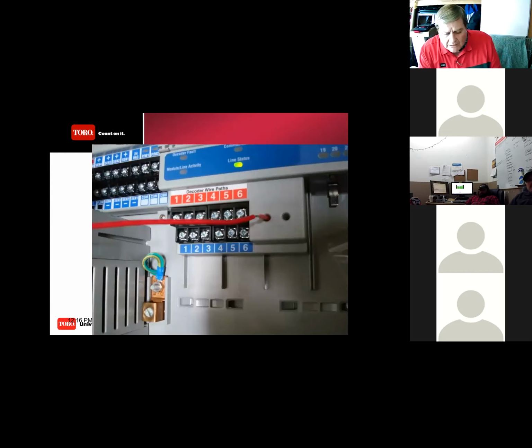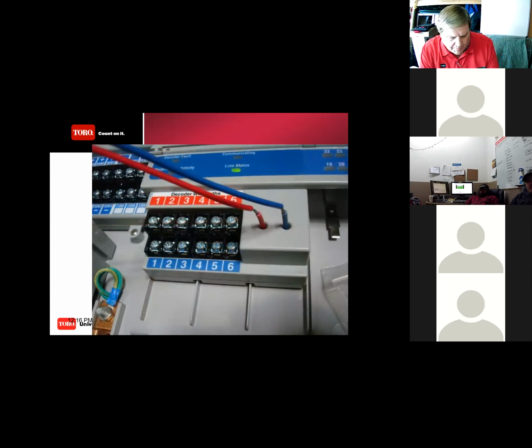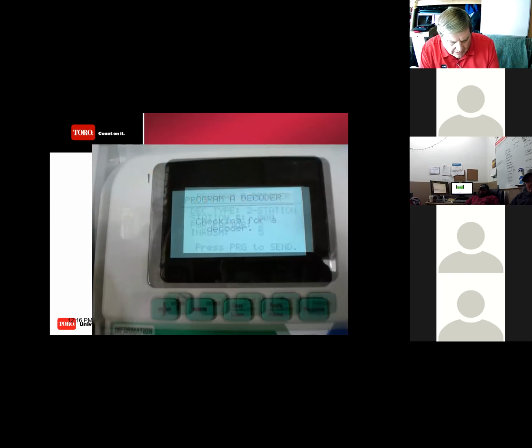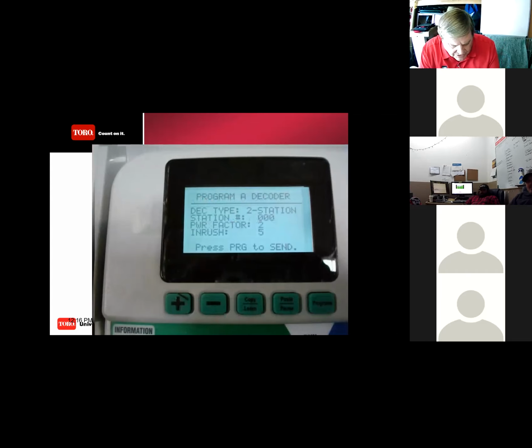Here's showing how they connect it up. You've got your red wire, you got your blue wire, you plug them into the appropriate slots. You go to the face of the controller, checking for a decoder. Sure enough, look at that, lo and behold, we have one. It's a 2-station version, power factor and inrush.